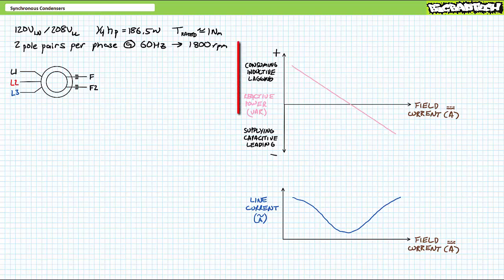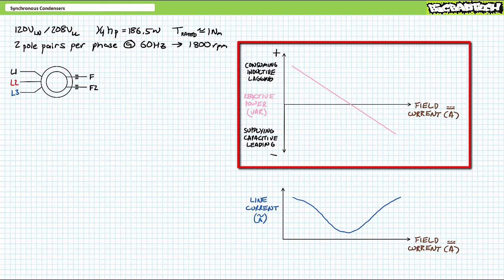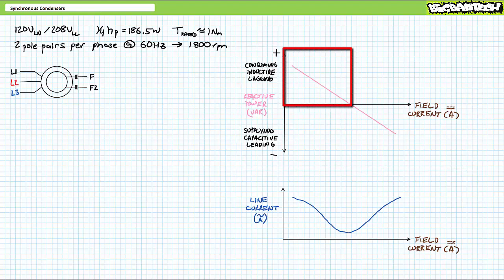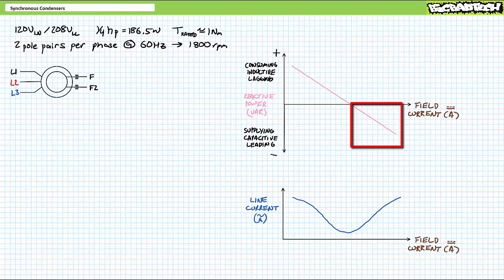In the aforementioned lecture, we learned that a graph of reactive power as a function of field current for an electrically excited synchronous motor looks something like this. At low levels of rotor excitation, the synchronous motor draws positive reactive power and appears as an inductive load where current lags voltage. If field current increases, it draws less reactive power and the phase shift between voltage and current decreases. If field current is further increased, the synchronous motor switches roles and instead supplies negative reactive power and appears as a capacitive load where current leads voltage.